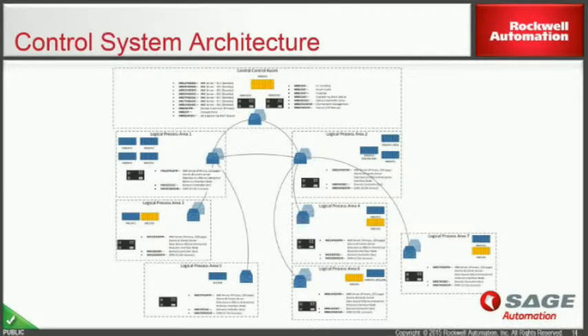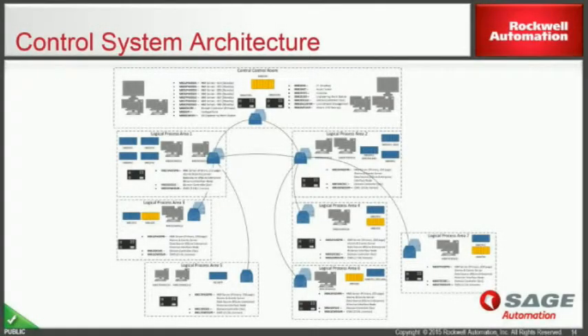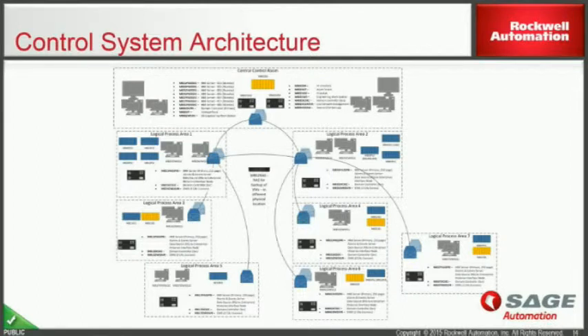Now, those 2 servers in the control room were in high availability mode. If one server physically fell down, the virtual machines running on that server would seamlessly be transferred and up and running on the other server without any loss of communication or function. And we had a combination of 4 thick clients in the control room, dual screen thick clients, 2 of which had a third 60-inch screen on the walls. And the process buildings had 9 dual screen clients amongst the local control rooms. And the whole system was backed up by a remotely located network access storage drive using the Veeam software.